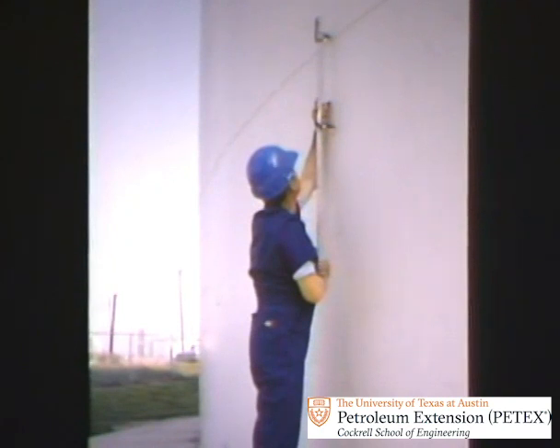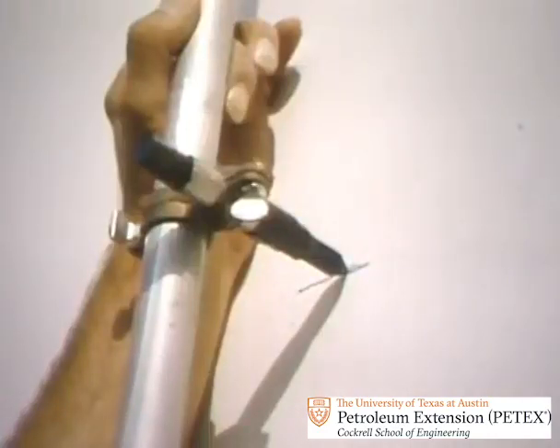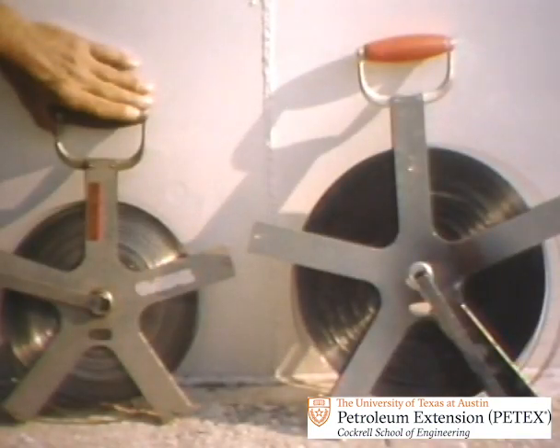Notice that he's marking the tape path on the bottom ring first. This is the ring to start on, and you'll see why in a minute. Once the tape path is carefully marked all the way around the ring, the crew gets its strapping tapes. They'll need 2 tapes. They'll use only one at a time, but the tape on the left is special. It's called a standard tape. The other one's called a working tape.